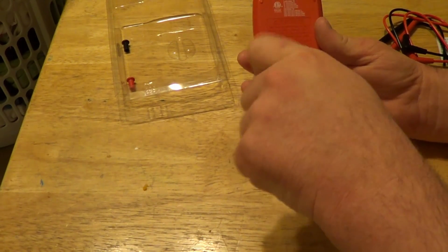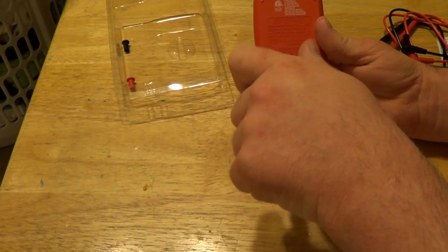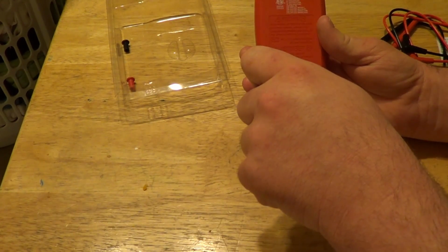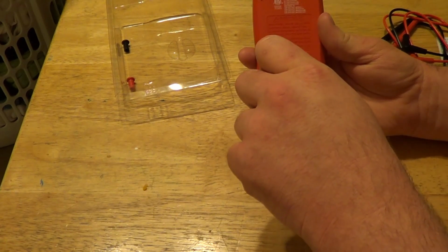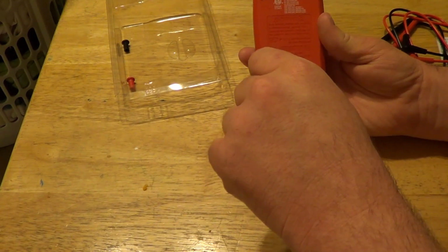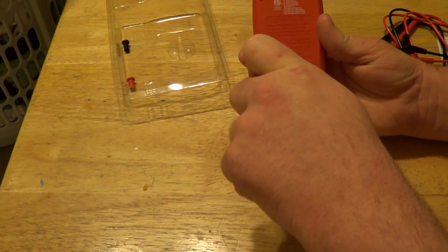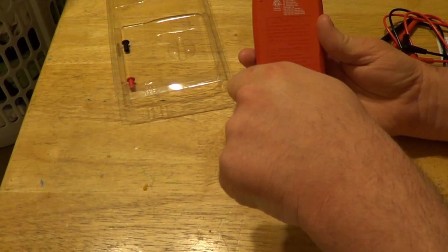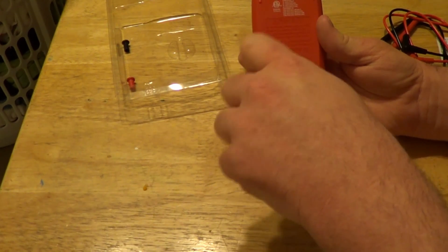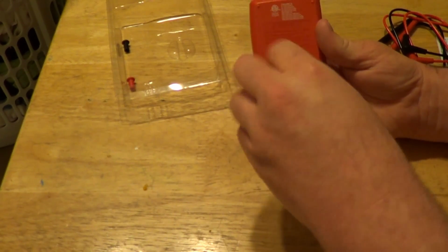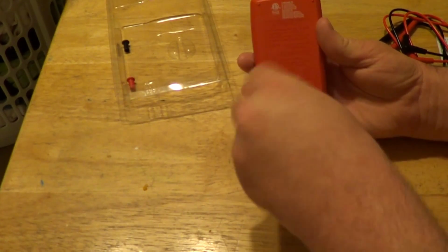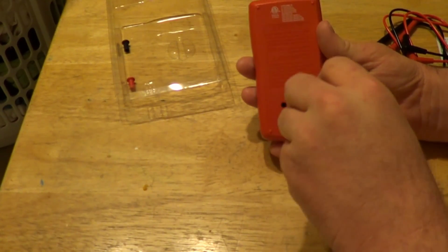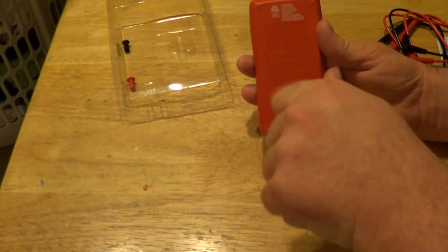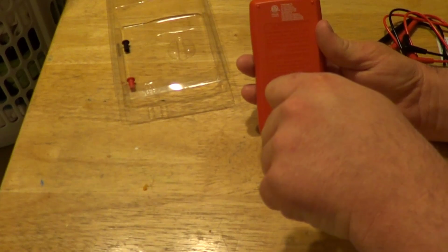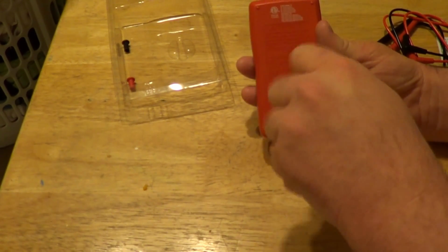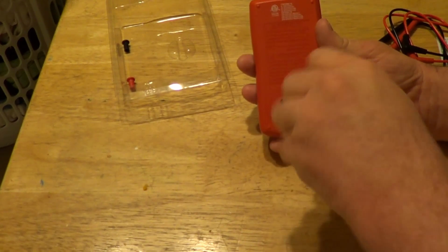The screws on the back cover of this meter only go into plastic, so make sure they've seated in their threads. It's very easy to do this even if you've never done it before: just turn your screwdriver backwards and listen for a click. When you hear that click, you can be fairly certain the screw has properly seated in the existing threads. If you don't do that, the screw might cut new threads, and eventually wallow out the plastic to the point where it won't screw in properly, or it might cause the plastic posts inside the meter to split apart. And then you'll really have a problem.